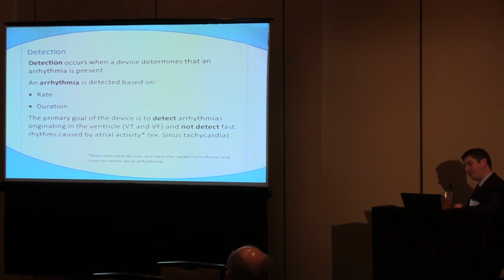So detection, like we said here, detection of the arrhythmia occurs mainly based on rate. You'll see that when we program these, we'll say you have a ventricular tachycardia setting or ventricular fibrillation setting at say 175 beats a minute or 200 beats a minute, which is what we normally program our primary prevention ICDs at, meaning that the treatment portion of the defibrillator won't be activated until the rate reaches that. Even if they have a ventricular tachycardia below that rate, it still won't be activated until the rate crosses that threshold.